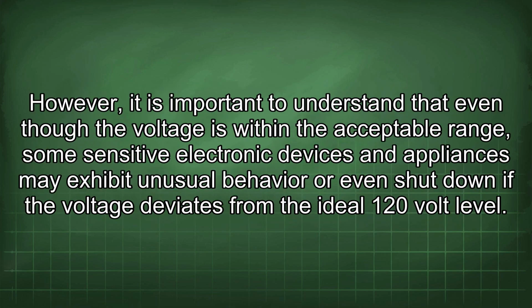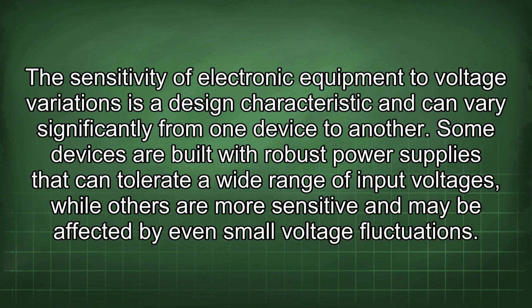However, it is important to understand that even though the voltage is within the acceptable range, some sensitive electronic devices and appliances may exhibit unusual behavior or even shut down if the voltage deviates from the ideal 120 volt level. The sensitivity of electronic equipment to voltage variations is a design characteristic and can vary significantly from one device to another. Some devices are built with robust power supplies that can tolerate a wide range of input voltages, while others are more sensitive and may be affected by even small voltage fluctuations.